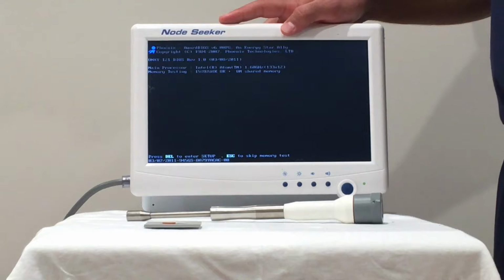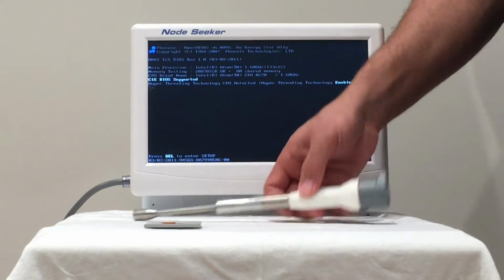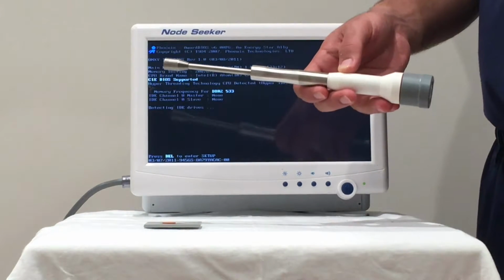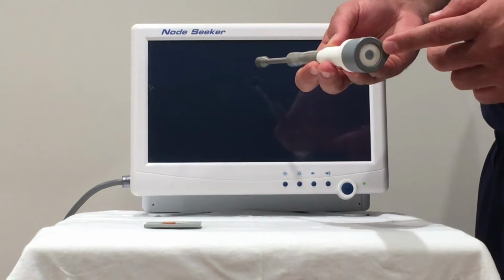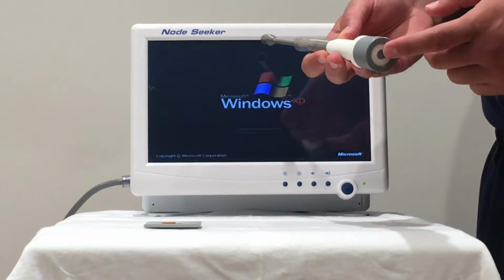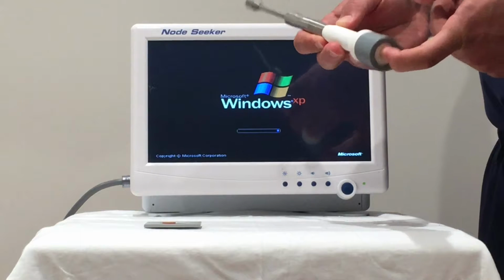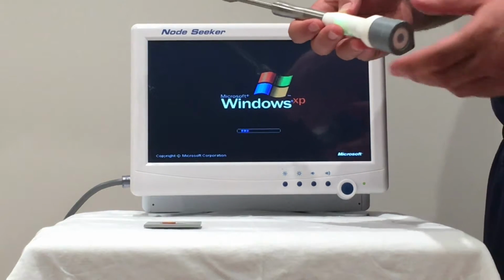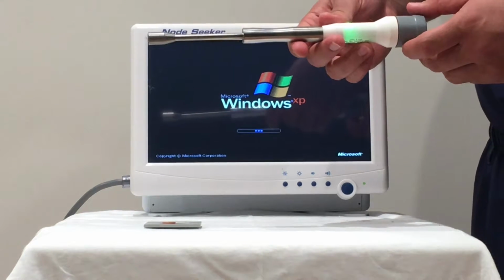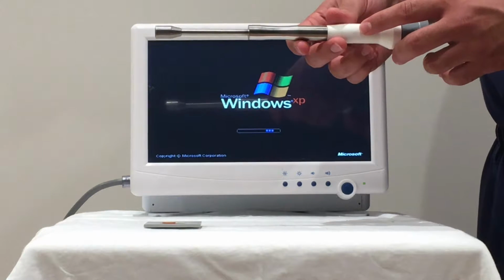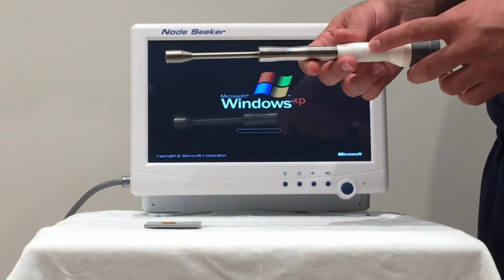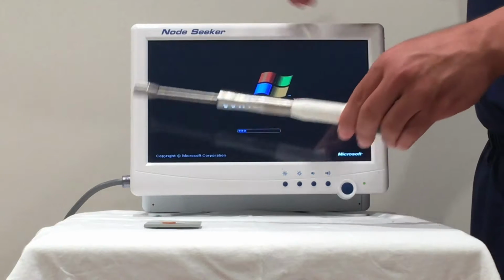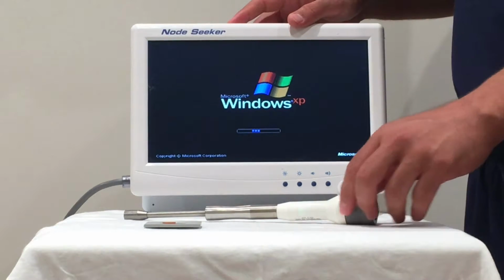As soon as we've turned on the control unit, we can go ahead and turn on our wireless Gamma Probe system. We can do that by tapping the black button at the bottom of the Gamma Probe. When we turn on the Gamma Probe, you should see a green light blinking at a steady rate. We'll give the system a few minutes to boot up.